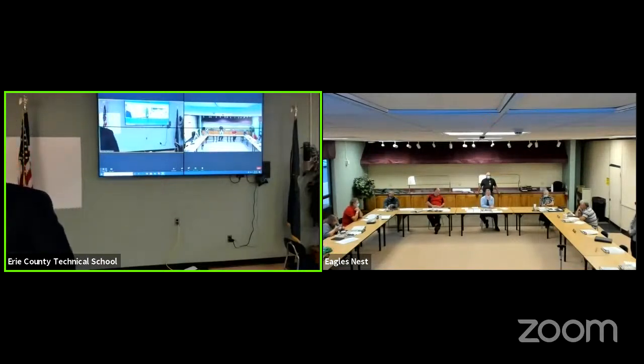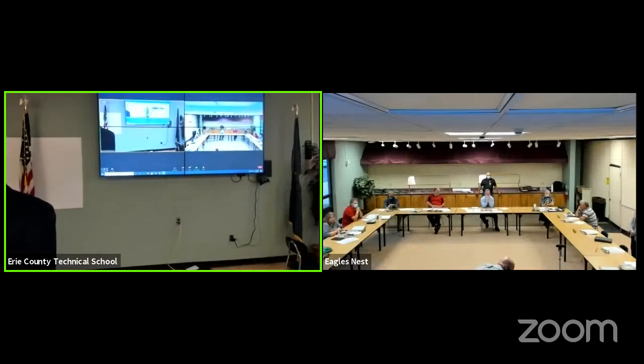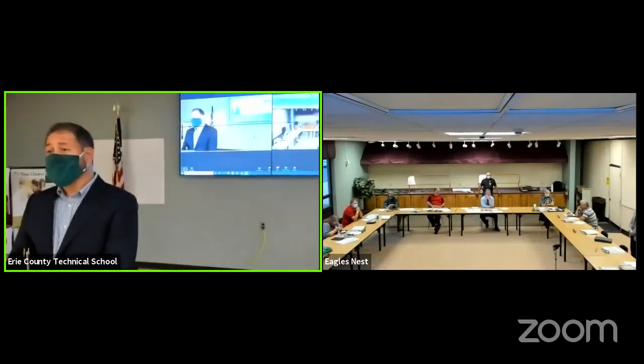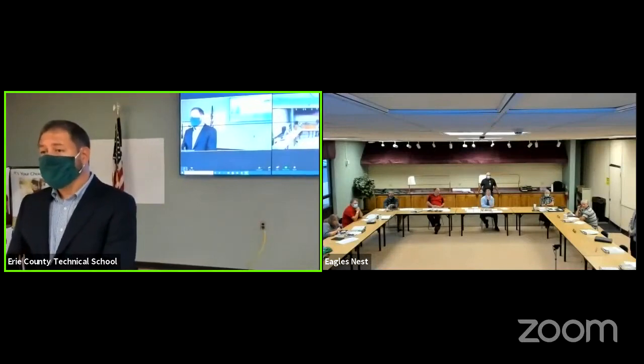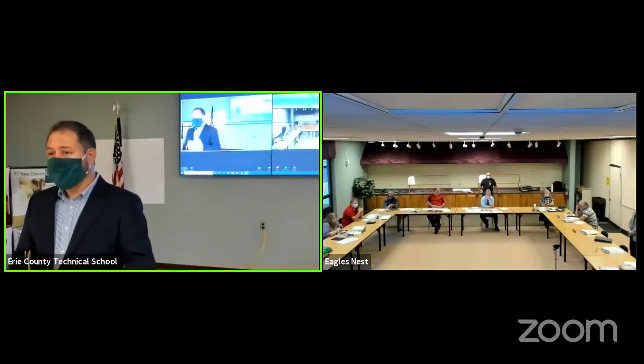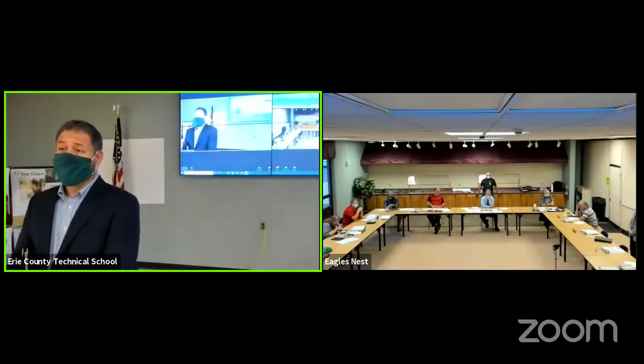With the equipment you're recommending, does it have the physical capacity to switch from those thinner filters to the bigger filters? Would there be enough ability to push that much more air through it, or would we need some other way to generate more air pressure? No, in fact we're already selecting the units for MERV 13, which is the recommendation, to make sure we have that extra horsepower and static pressure needed to incorporate those filters.